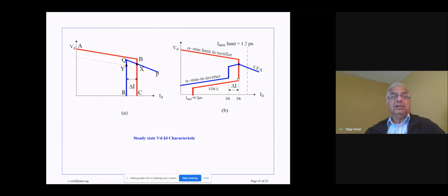So what are these modifications? You can see over here, the maximum current limit is shown as 1.2 per unit. So we don't want to exceed that. This is the protection system that we want to make sure that the valves are safe. This characteristic, which is the AB characteristic, is also called the alpha min limit characteristic for the rectifier end. This characteristic PQ, which is shown over here, is the constant extinction angle characteristic, and the operating point is indicated. The margin is there, and we have this characteristic for the inverter.